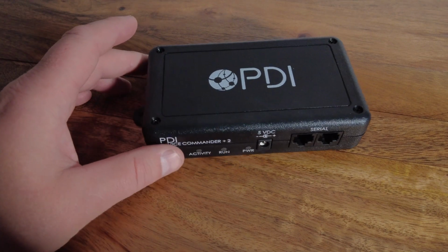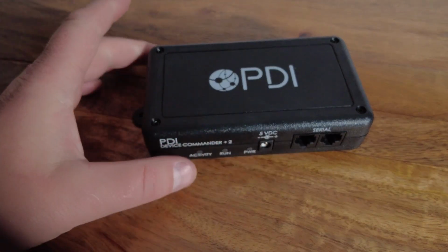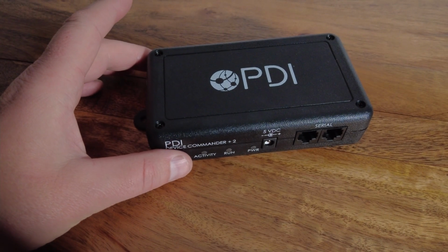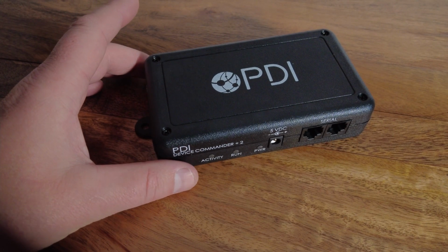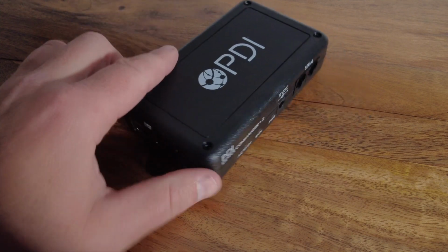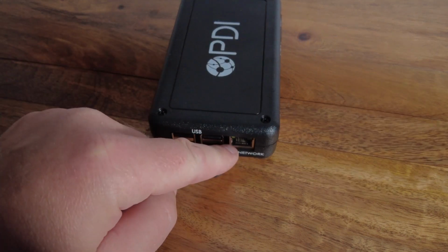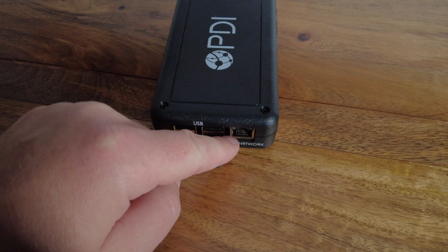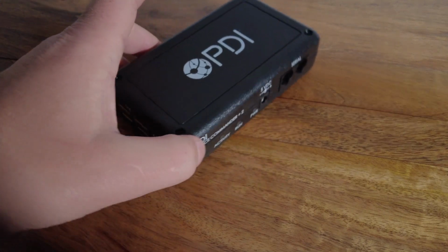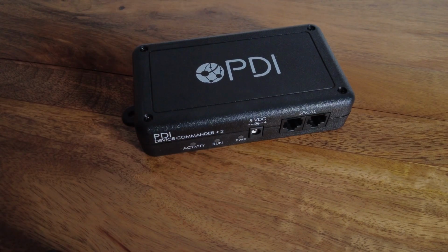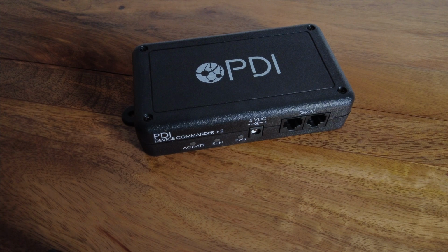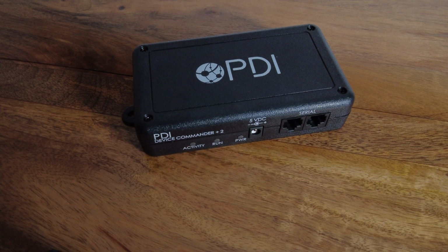Basically, the way this one works is you're going to use one of the serial adapters to connect whichever cable you need to connect to your tank monitor, and then you are going to plug this via the Ethernet cable or network cable into the site's ISP, and then you're going to call PDI, and PDI will connect into the device via a VLAN connection, at which point they will configure it to match whatever baud rate and serial settings you have set in the tank monitor so they can connect in.